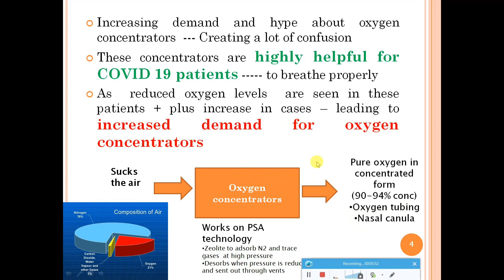There are various parts, like the oxygen tubing and the nasal cannula, which help in the transfer of this oxygen to the patient. This is a SEM image of a zeolite, just to show you that these zeolite materials are porous in nature. You can see how the porous material is there. This porous nature will help in adsorbing the gas molecules. They will trap these gas molecules, especially nitrogen and other gases which are not good, and we finally want only oxygen. All these gases will be trapped, and finally you can send them out, and the oxygen in its purest form with high concentration, whether 90 or 95%, can be given out.